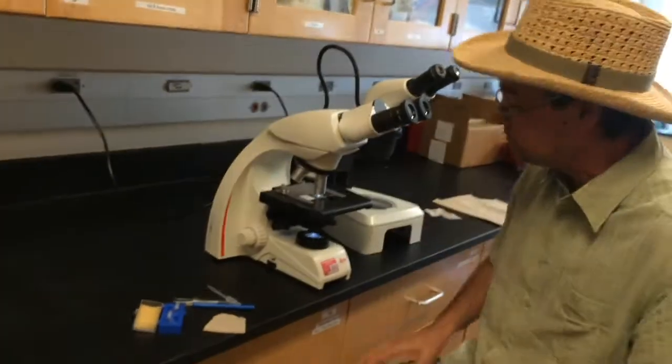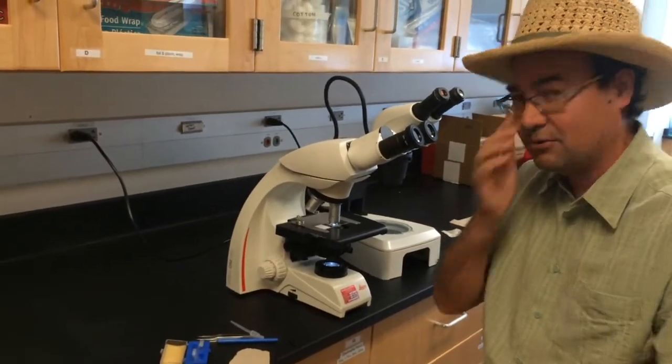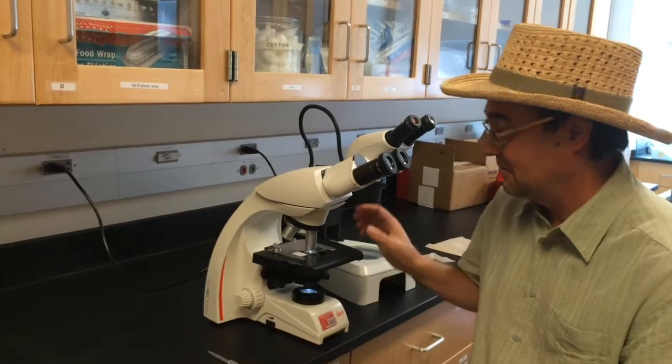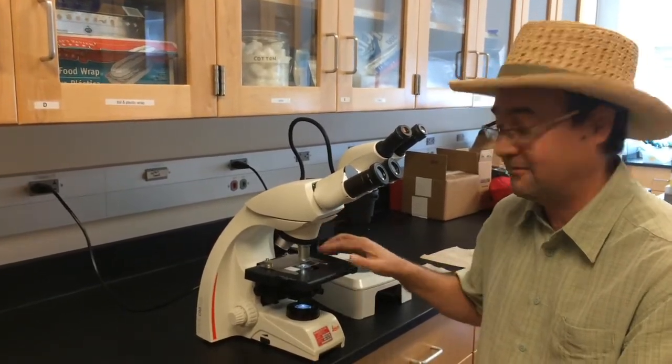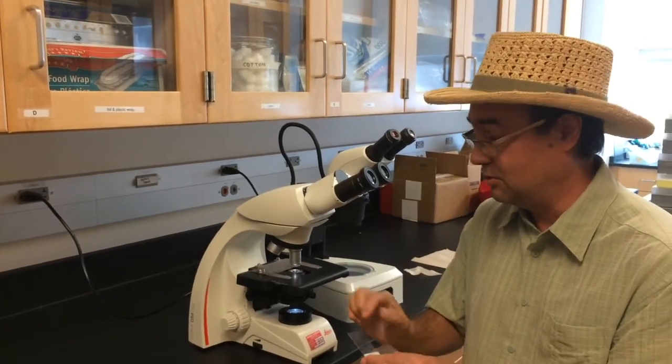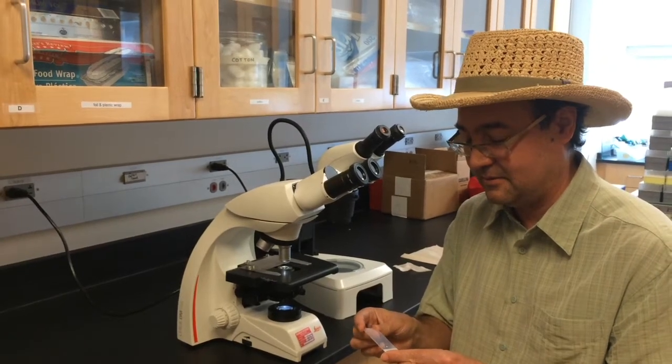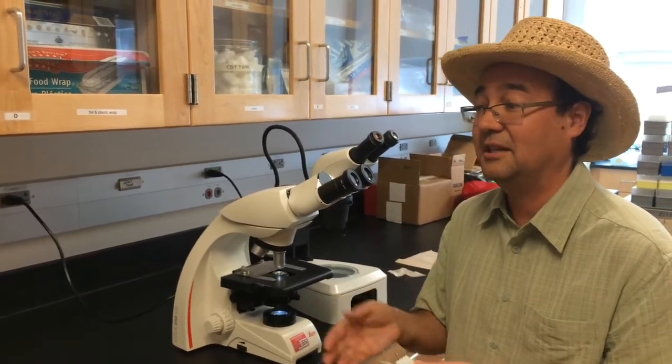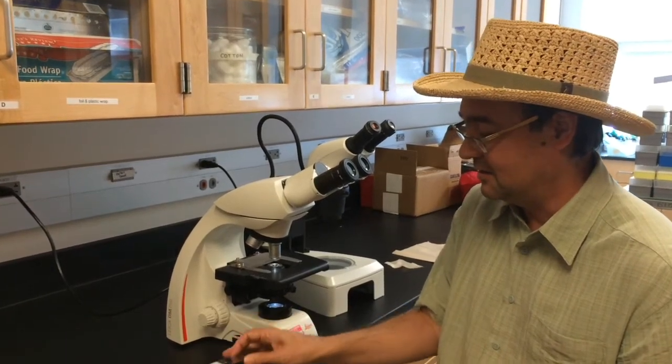Okay, so you do your thing, and then you're ready to change slides. And here's what I want you to do for me. Always rotate this back down to a shorter objective before you yank off the slide. That way we don't get goo on the high power objective, which means we don't have to clean it, and it doesn't get damaged, and it doesn't drive me crazy.